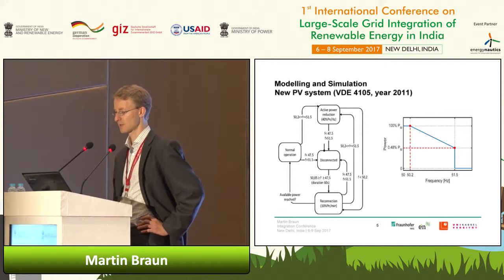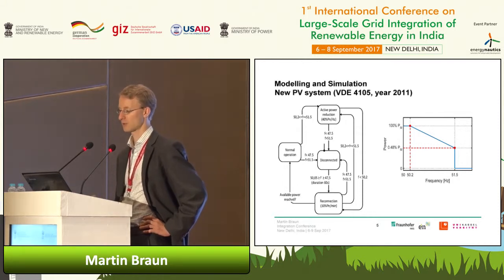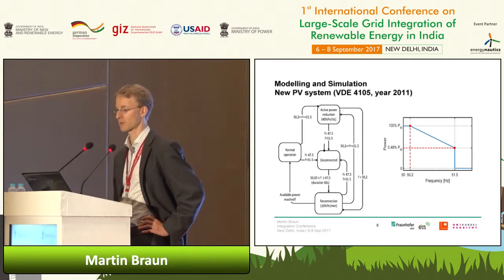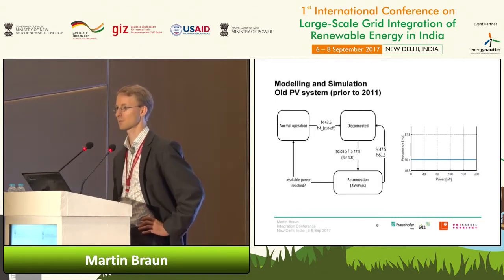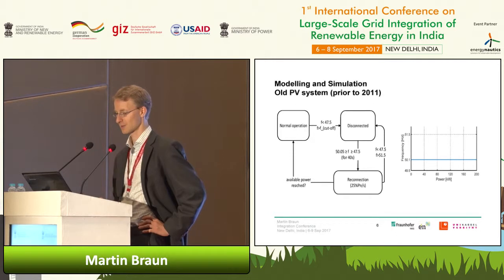So here you see the dynamic reduction of active power depending on the frequency. So this is quite important. You see the difference if we look at the old systems. The old system looks much easier to model in the state diagram, which means that in case we have a defined cutoff frequency, the system is just disconnected.